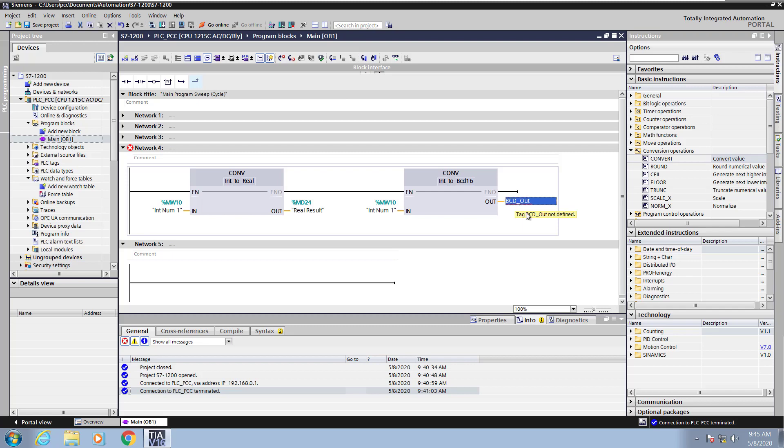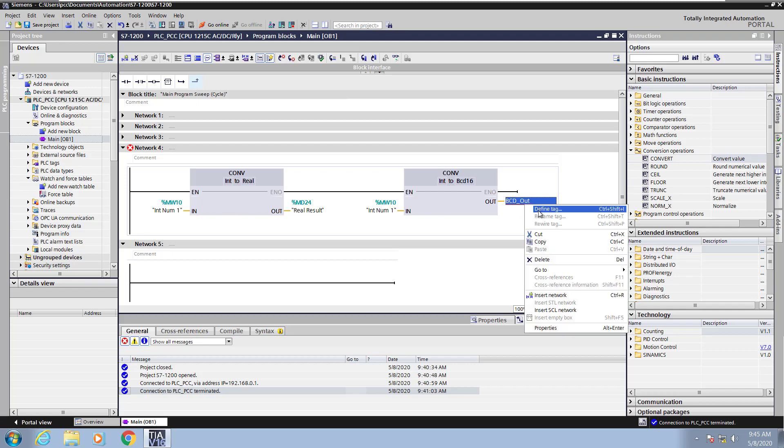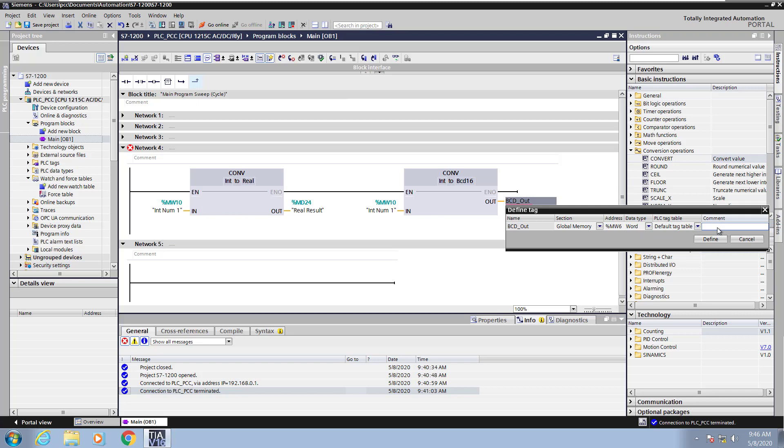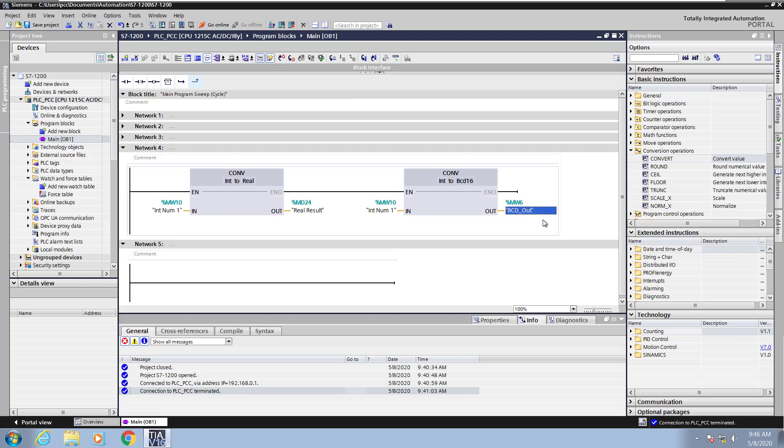You'll see the red squiggly lines. The tag is not defined, so I will right-click on the tag and select Define Tag. In the section here, I'm going to pick Global Memory, and it will pick the next available M address. I'm going to use the word Data Type because there's not a BCD data type inside the controller. So I'm going to enter in a comment here to indicate that as well, and then I will click Define. This creates the BCD tag.